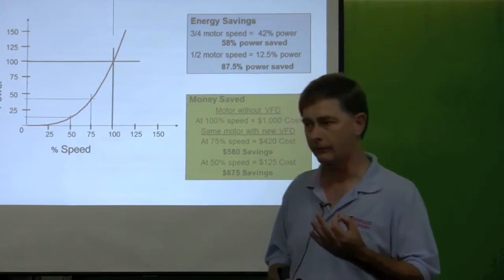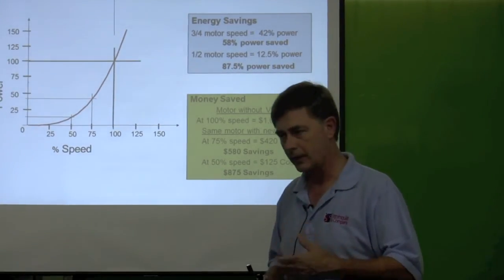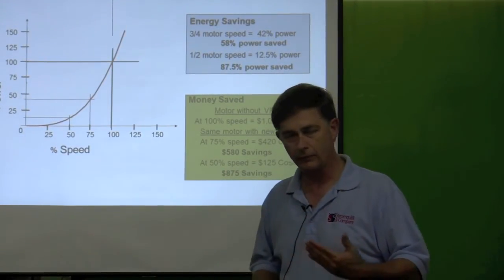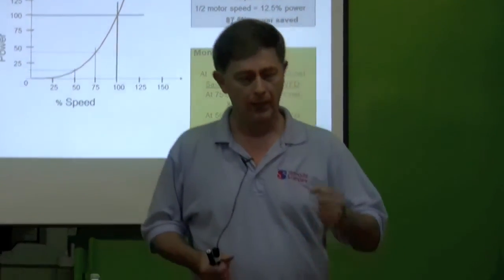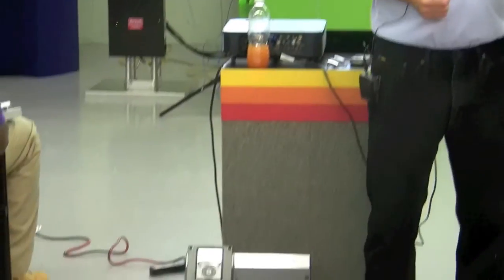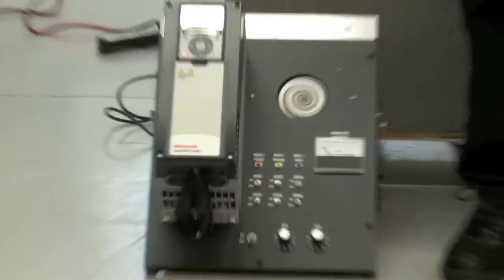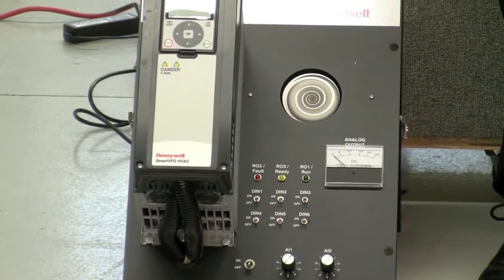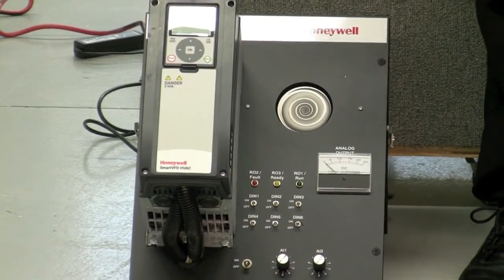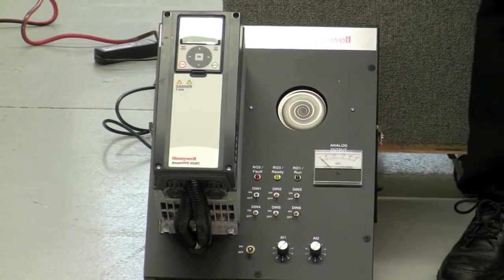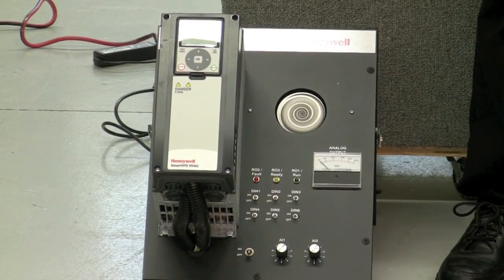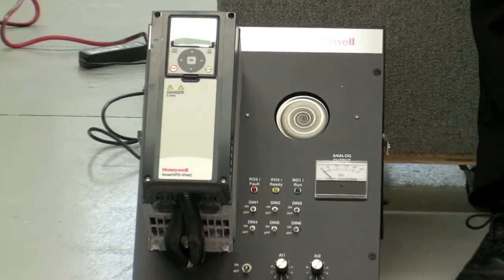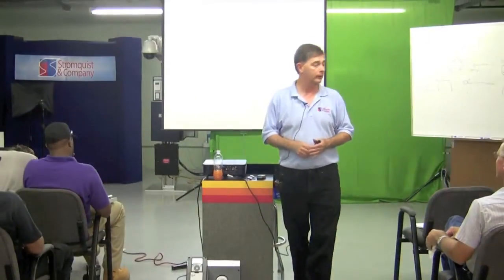There's another advantage to these things. You've got a built in soft start component. If you've got a big 50 horse motor on the air handler or pump, and that contactor pulls in, you've got a lot of forces on that equipment. Frequency drive, when it pulls in to start that motor, you're going to start it up over 5 seconds, 15 seconds, 30 seconds, a minute, whatever the case may be.